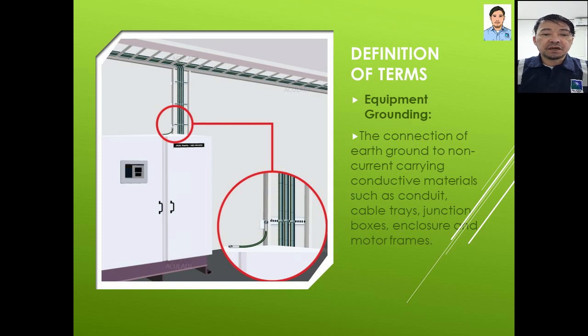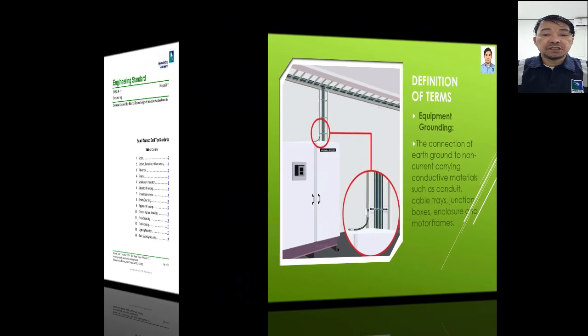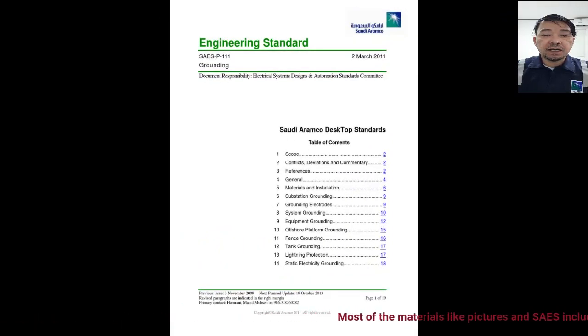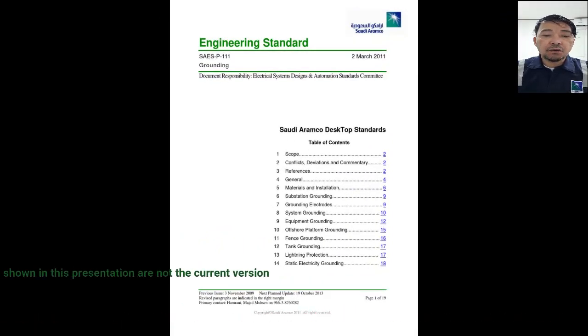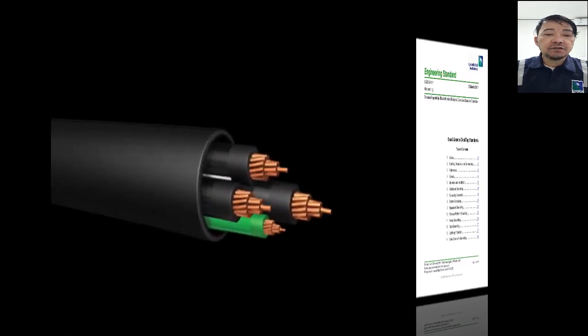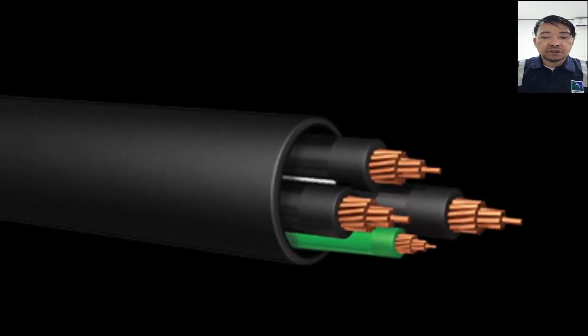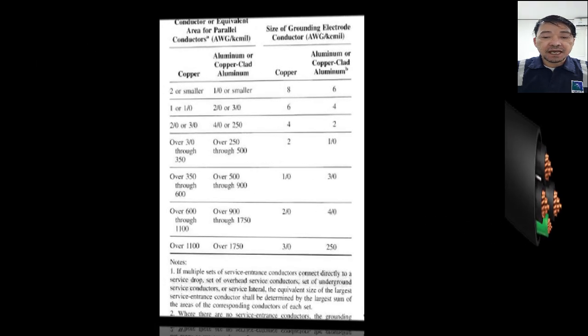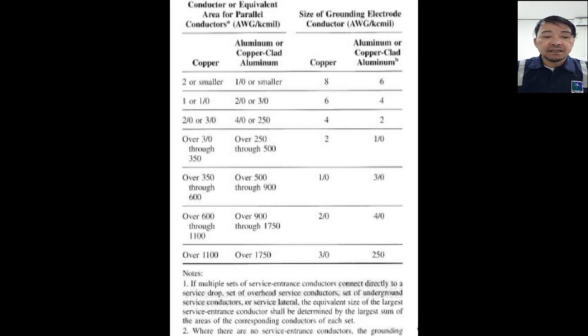Let's discuss the equipment grounding requirements. These requirements are under Section 9 of SAES-P-111. In hazardous locations, equipment grounding conductors run in conduit or cable tray shall be insulated. These conductors shall be sized in accordance with NEC Table 250-66 for the largest power conductor in the tray, with a minimum size of 25 mm squared or equivalent to number 4 AWG.